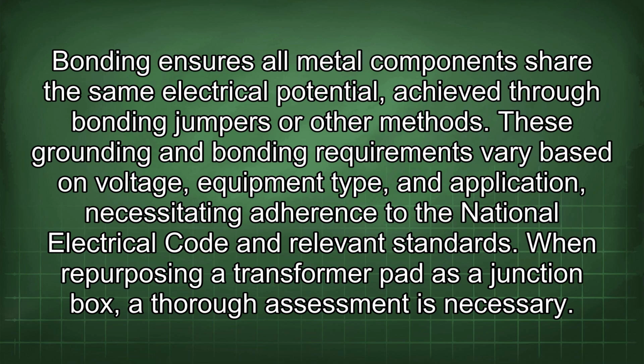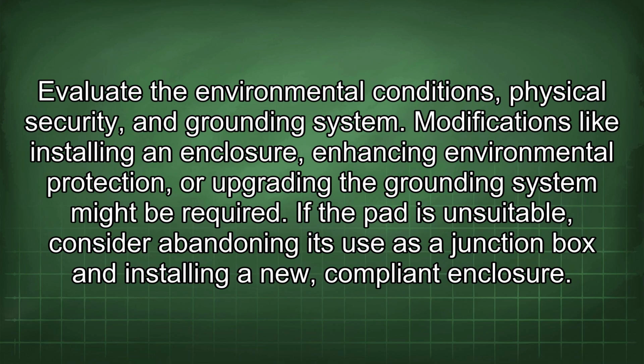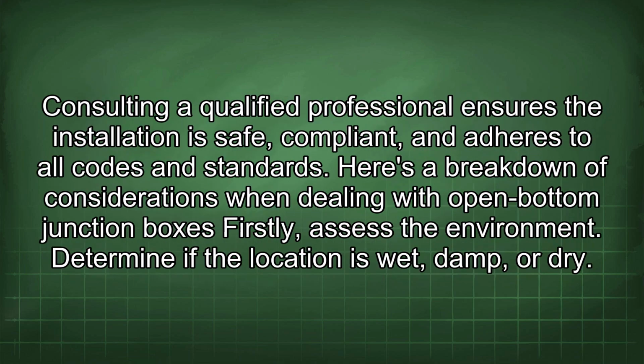These grounding and bonding requirements vary based on voltage, equipment type, and application, necessitating adherence to the National Electrical Code and relevant standards. When repurposing a transformer pad as a junction box, a thorough assessment is necessary. Evaluate the environmental conditions, physical security, and grounding system. Modifications like installing an enclosure, enhancing environmental protection, or upgrading the grounding system might be required. If the pad is unsuitable, consider abandoning its use as a junction box and installing a new, compliant enclosure. Consulting a qualified professional ensures the installation is safe, compliant, and adheres to all codes and standards.